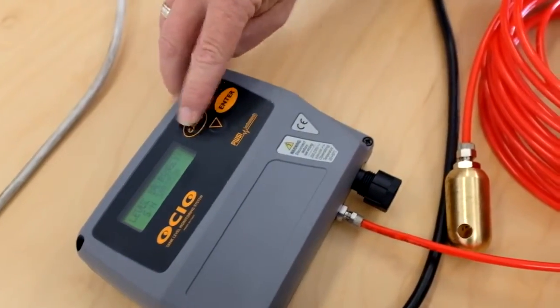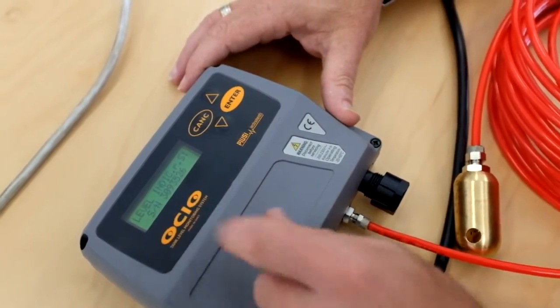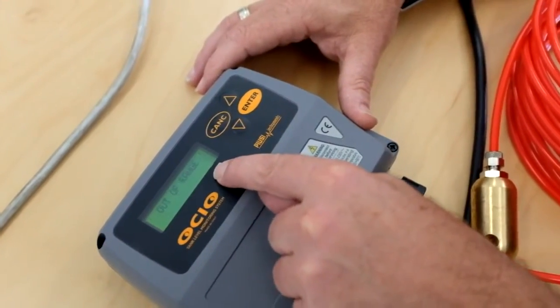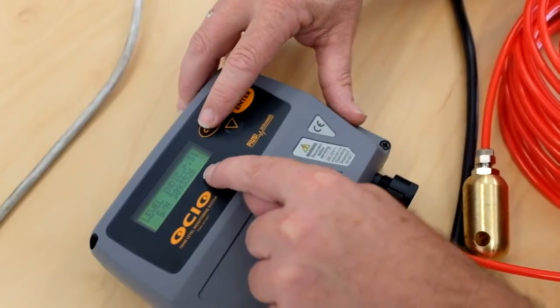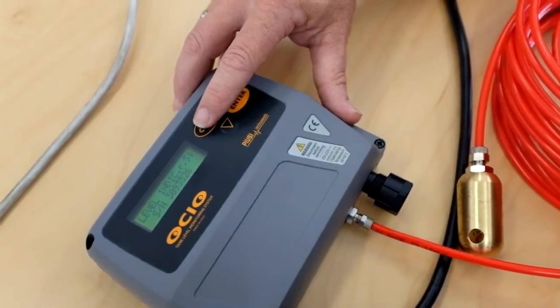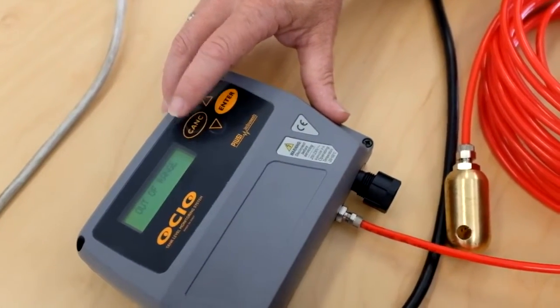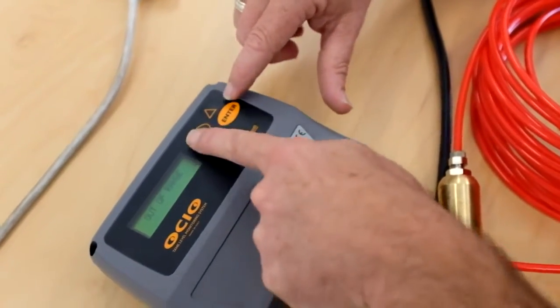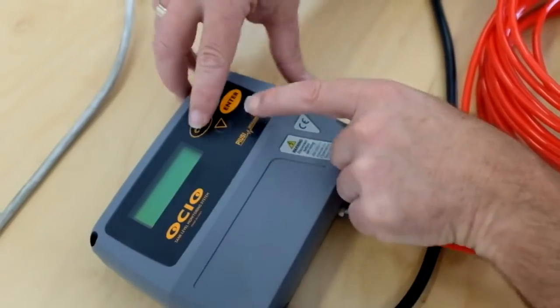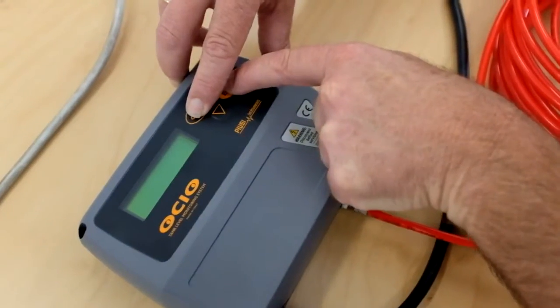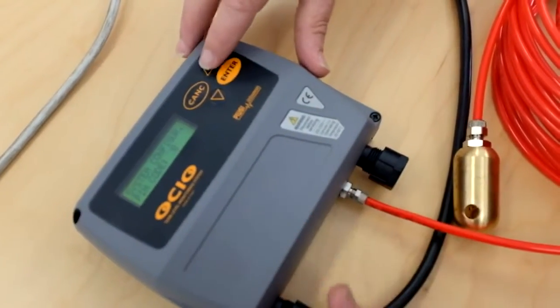We hit the cancel button and we can see the serial number of the unit. The last two numbers are significant. You need to know the last two of each unit and the individual. So this one was 26. To calibrate it, we're going to hold down cancel and enter. We're into the configuration mode.